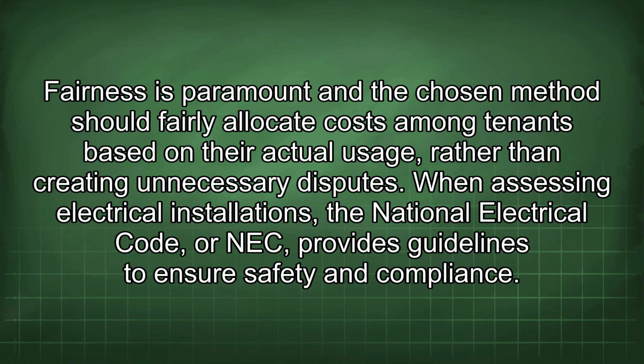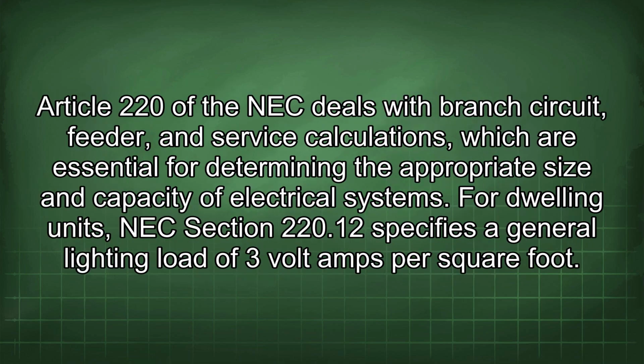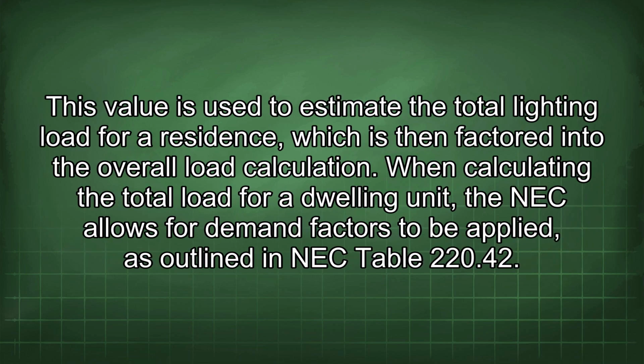When assessing electrical installations, the National Electrical Code, or NEC, provides guidelines to ensure safety and compliance. Article 220 of the NEC deals with branch circuit, feeder, and service calculations, which are essential for determining the appropriate size and capacity of electrical systems. For dwelling units, NEC Section 220.12 specifies a general lighting load of 3 volt-amps per square foot. This value is used to estimate the total lighting load for a residence, which is then factored into the overall load calculation.